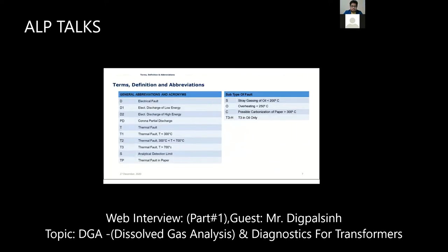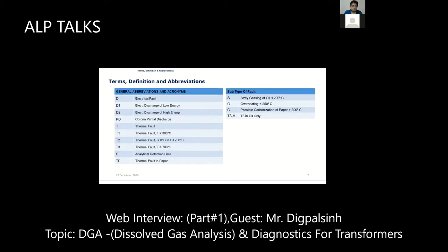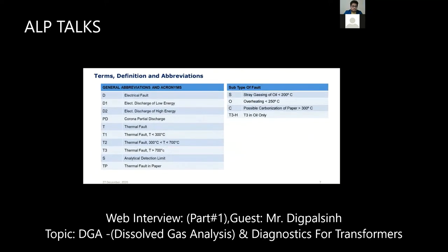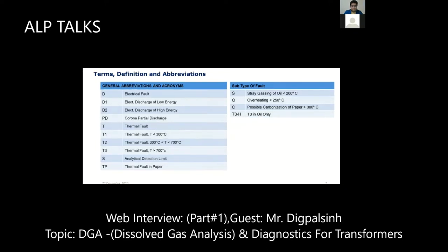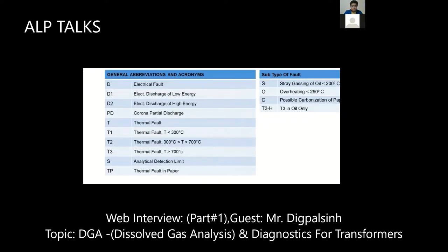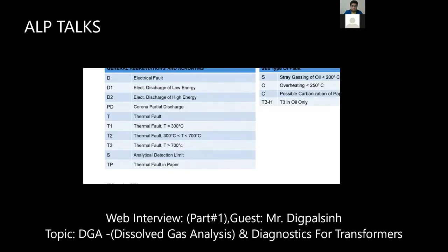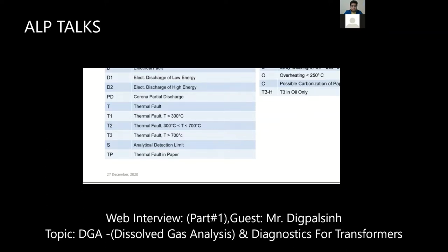These are the main abbreviations, the defined numbers for the faults by CIGRE and accepted by IEC and IEEE. D1, D2: D is for electrical fault, D1 for electrical discharge of low energy, D2 for high energy discharge. PD is corona or partial discharge. T is the thermal fault; T1, T2, T3 are categorized based on the temperature value: below 300, 300 to 700, and more than 700. S is the analytical detection limit and TP is the thermal fault in paper.